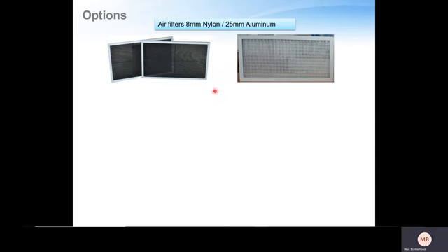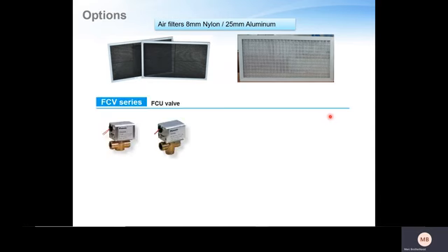Optional air filter nets as well as aluminium grating can be further optional extras on these ducted fan coil units. We also offer two-way valves as well as three-way valves. These are obviously going to be a decision depending on the strategy and the hydrodynamics of the system. So if we want three-way valves, we would typically select this valve for designs where there are constant speed pumps in the plant room. A three-way valve will always maintain a constant volume or mass flow rate of water.